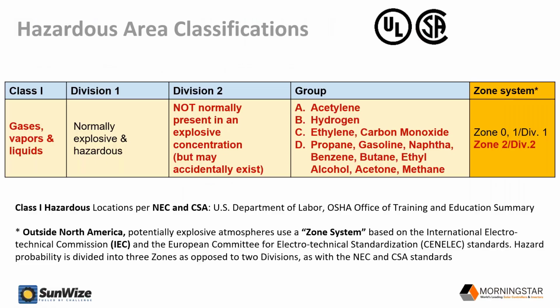So what a hazardous area classification really covers, to break it down, is two types of environments that we're talking about. First, the class we're talking about is gas, vapors, and liquids, which covers most of these applications. Division 1 is an area where it is normally explosive and hazardous, such as something operating inside of a tank where it's exposed to this environment all the time. It is assumed that it is surrounded by an explosive gas. What Morningstar's products are rated for is Division 2, which means that they are near to that application. Explosive gases are not normally present in an explosive concentration, but that type of environment could exist if there was a leak or a malfunction, and therefore the product needs to be designed safely and certified correctly so that if that occurrence did happen, the product would not contribute to an explosion.